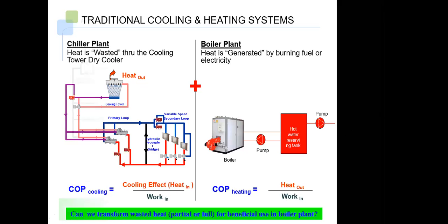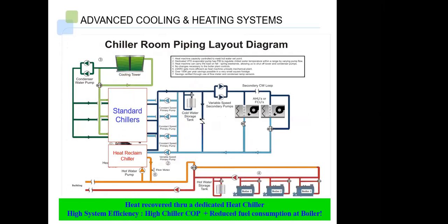COP, and which is being explained in this slide. So it's the same plant doing the same thing, but apart from the standard chillers which are doing the cooling application, we add a chiller which is called a heat reclaim chiller. So what does this chiller do? It produces a high temperature hot water for the system.